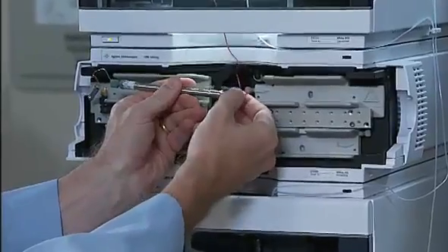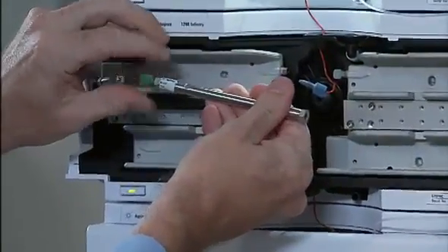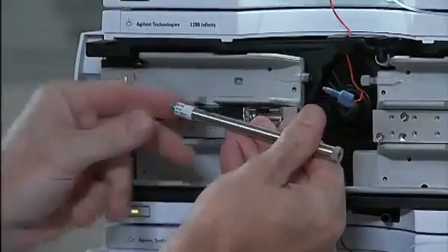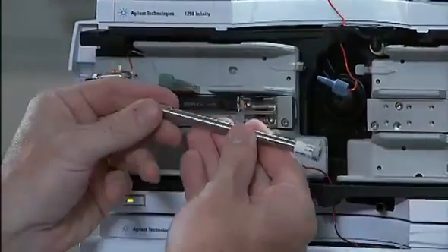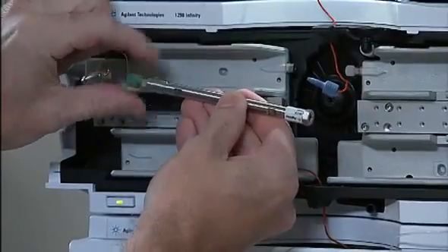One of the things you should try to do if you think you have a contamination from previous injections is to backflush your column. I discussed this process pretty thoroughly in the segment we did on pressure changes. When you clean your column, wash with a solvent that is stronger than your mobile phase. It's a good idea to take your detector out of the flow path before rinsing.